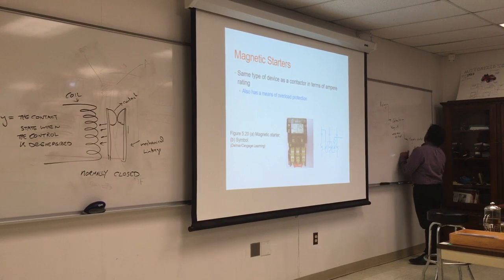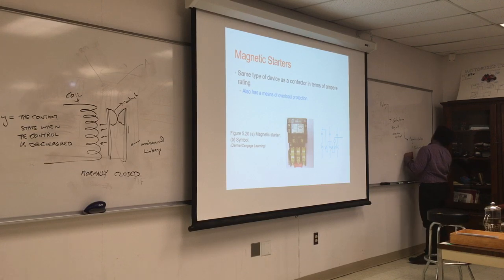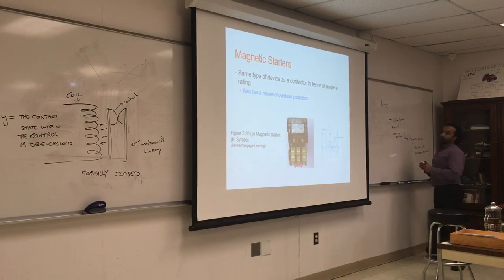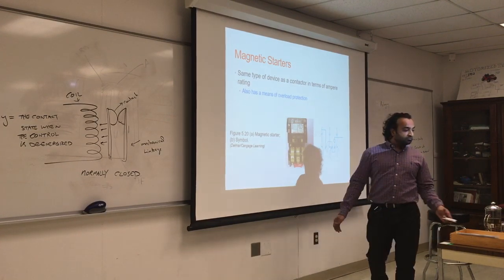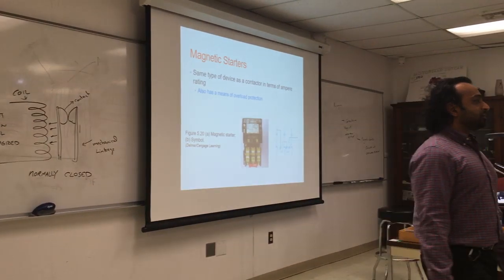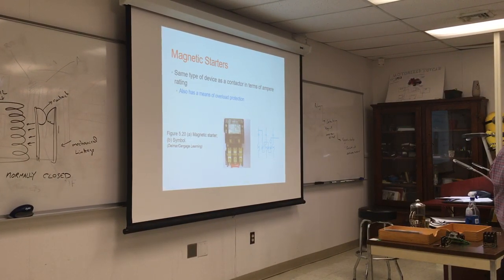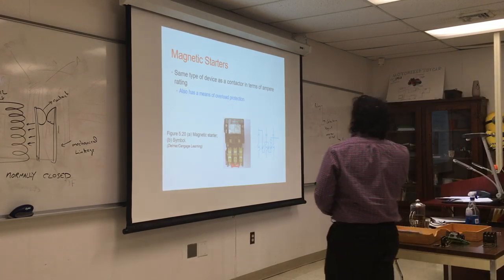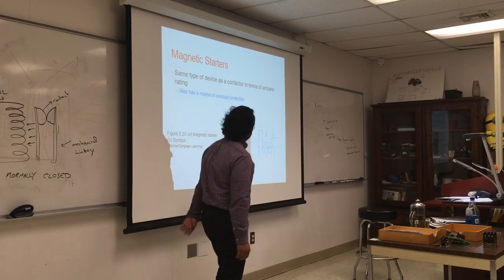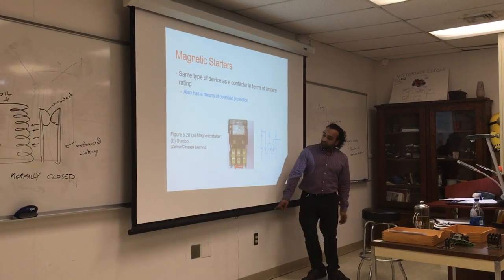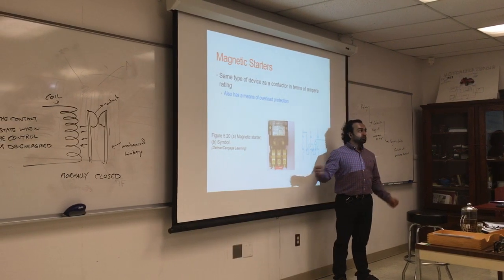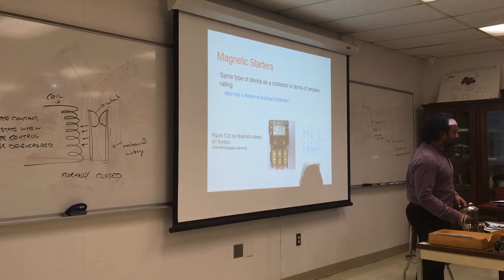A magnetic starter is a contactor with overload protection. It's a huge thing used for big motors, more than 20 amps, where you want some kind of safety. If you exceed the overload, it should trip by itself. This is what it looks like normally, and it's quite huge. You reset it by pushing those buttons down, and it will pull out whenever you have excess load.